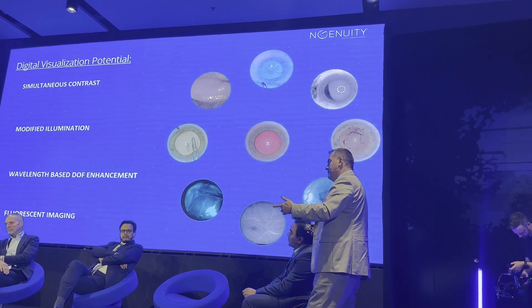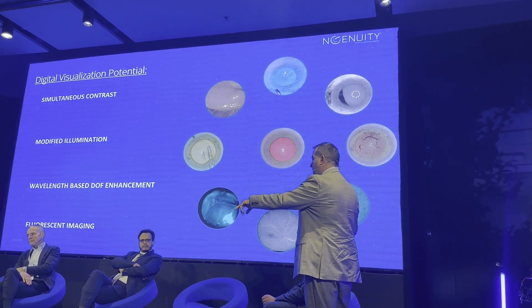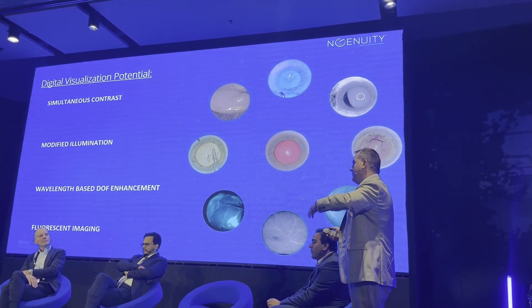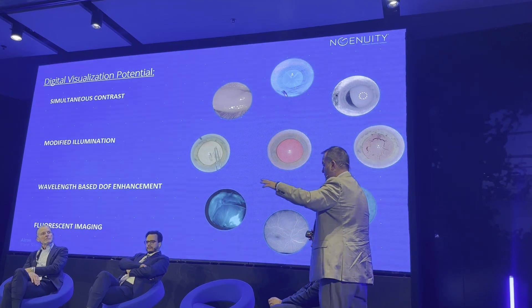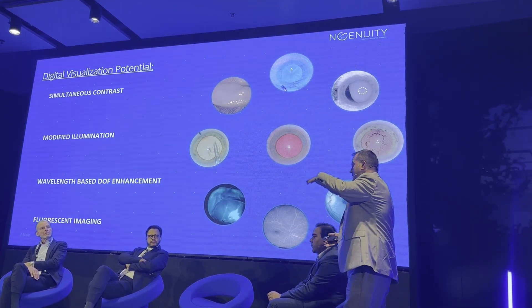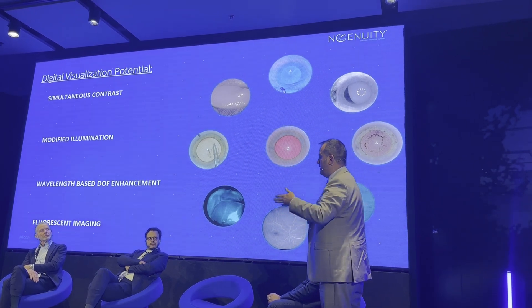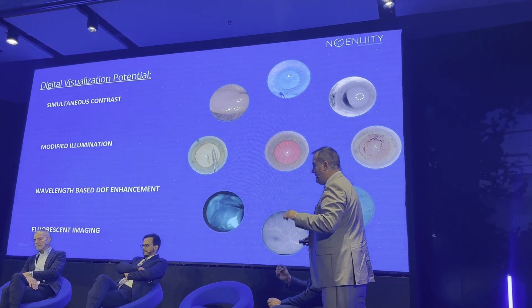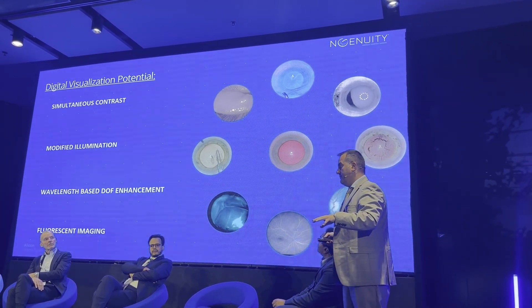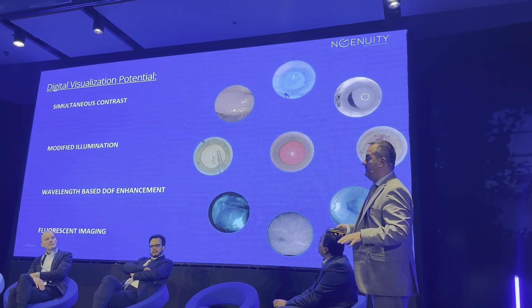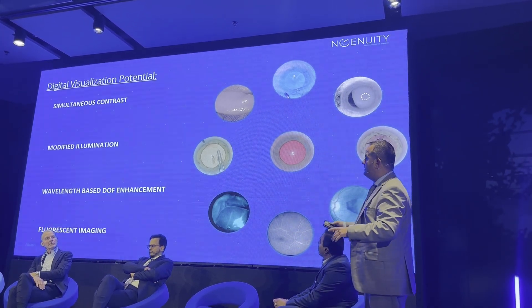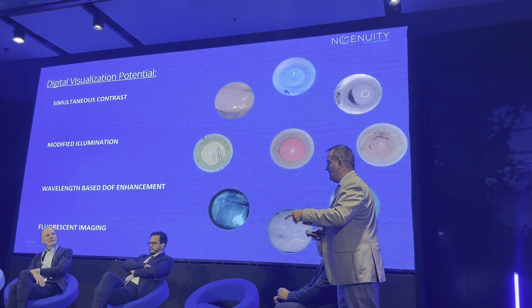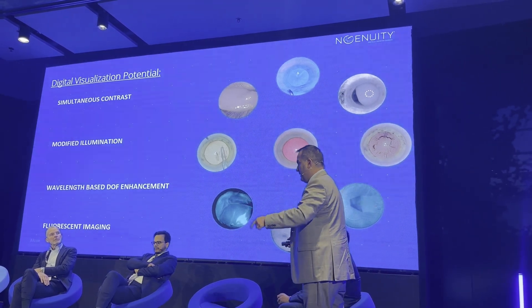I rely on simultaneous contrast concept. I modify the illumination, and as Sumit pointed, we can play with the wavelength to increase the depth of field. This is a well-known concept in multi-focal lenses — EDOF creation with a clever combination of wavelength of light. Last but not least, NGENUITY is the only digital visualization system in our field which can provide fluorescent imaging, meaning we can have real-time navigation and functional data.